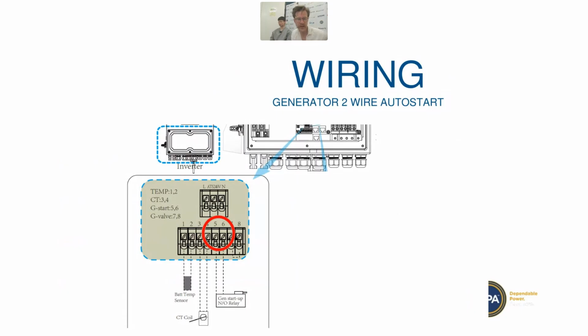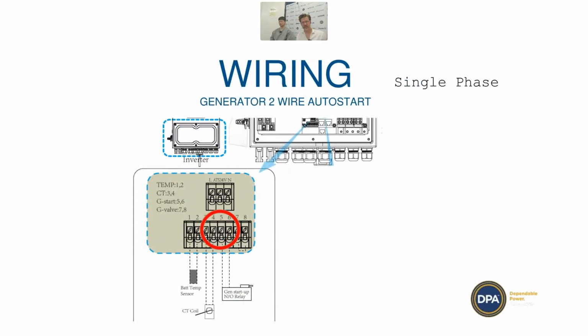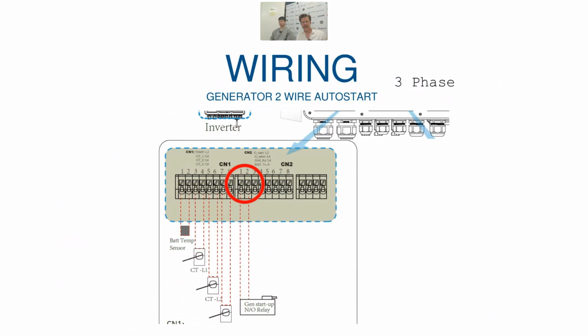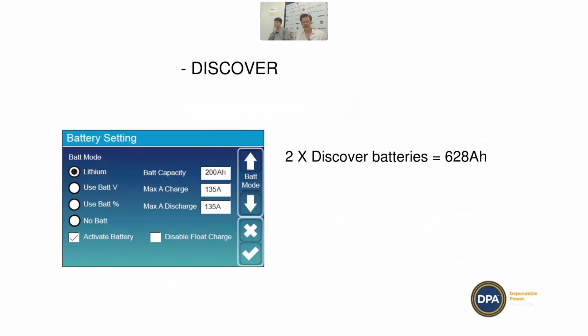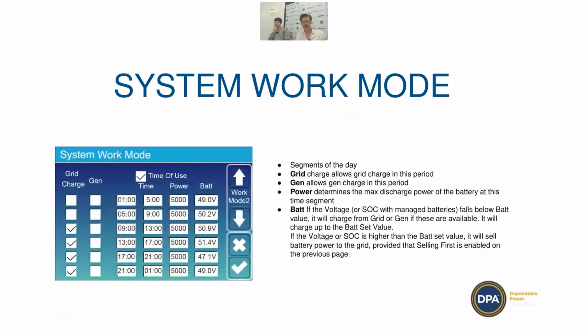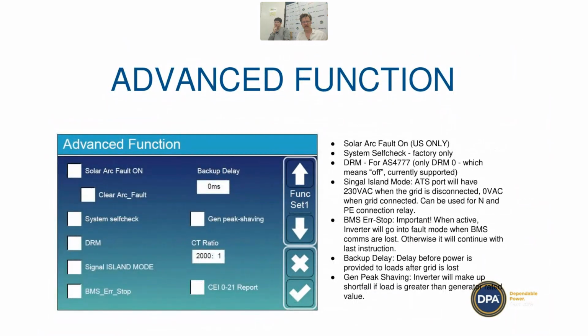So it's a normally open relay, and that's just for a 2-wire auto start for the generator. And that will start the generator once it gets to the set threshold that we saw at the beginning. And I'll see if I've got a slide for that. No, I don't. So when we set up the generator charge and the grid charge, there was an option for generator signal. You need to tick that in order for it to use this dry contact. And so when it gets below the threshold that you set in that menu, let's go back to that, shall we? I think this is important. Then it's going to trigger the generator to turn on.